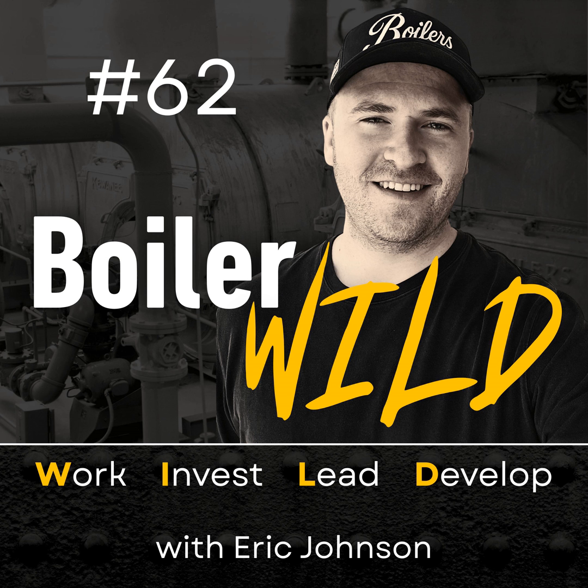And I'm going to tell this podcast kind of from a service perspective, but if you're an in-house team or like a stationary engineer, you can still do the same troubleshooting perspective, but you will have a little bit more leniency because you'll be around the equipment all day and you can more so watch the equipment and be able to figure out what's going on rather than a service tech showing up and having to diagnose the issue right then and there, leaving, and then waiting for a call back to see if the problem goes away or not.